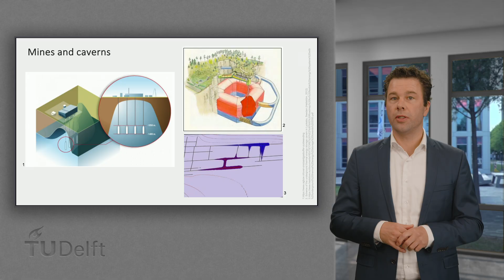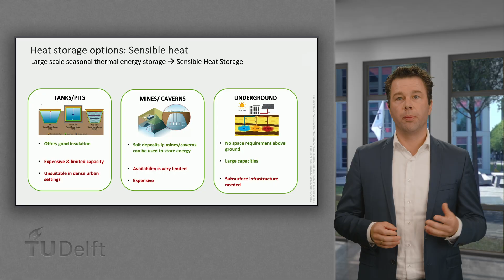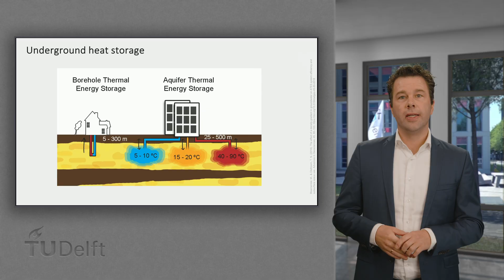The last sensible heat storage option is the subsurface. Naturally occurring layers are used to store heat at depths of about 50 to 400 meters. The advantage is that they are cheap to make and have a small footprint at the surface. Their applicability depends on the local geological conditions. Here we distinguish between borehole heat exchangers and aquifer thermal energy storage systems.